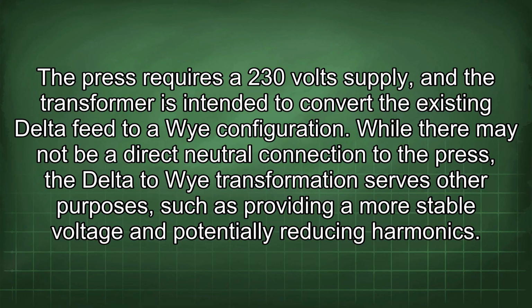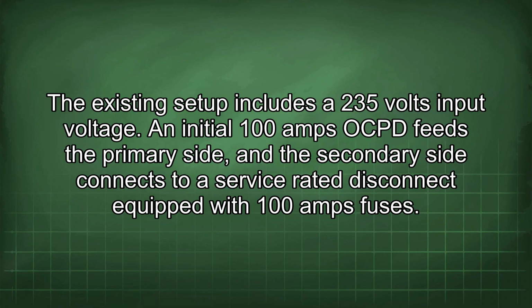The press requires a 230 volts supply, and the transformer is intended to convert the existing delta feed to a Y configuration. While there may not be a direct neutral connection to the press, the delta to Y transformation serves other purposes, such as providing a more stable voltage and potentially reducing harmonics. The existing setup includes a 235 volts input voltage.